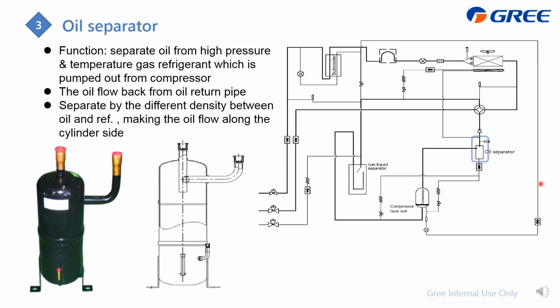Oil separator located here, which is at the discharge of the compressor. The purpose of this one is to separate the oil from the high pressure and temperature gas, which can prevent the oil from getting into the system and also make the oil flow back to the compressor for lubrication. For GMV5 we have two oil separators, but for GMV6 there is only one, but we create another oil return passage. The oil which is separated from here will have two passes to flow back to the compressor and back to the oil separator, which is this one.